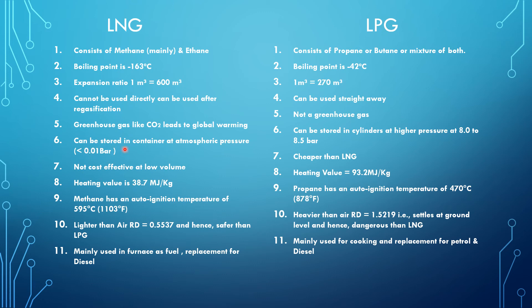LNG can be stored in a cryogenic vessel at atmospheric pressure or low pressure of less than 0.01 bar (10 kilo Pascal), whereas LPG is stored in cylinders at a higher pressure of 8 to 8.5 bar. In terms of cost, LNG is not cost effective at low volumes — it is costlier for cooking or heating — whereas LPG is cheaper for low or higher volumes and is commonly used as cooking gas.